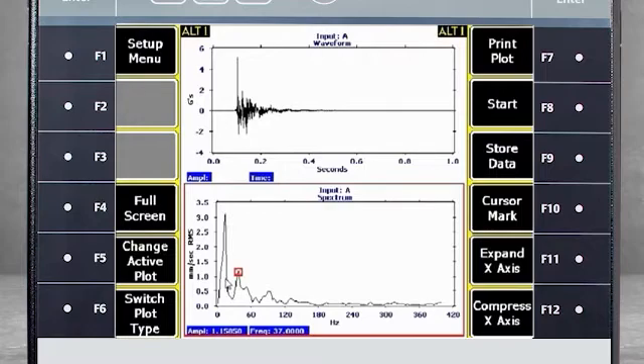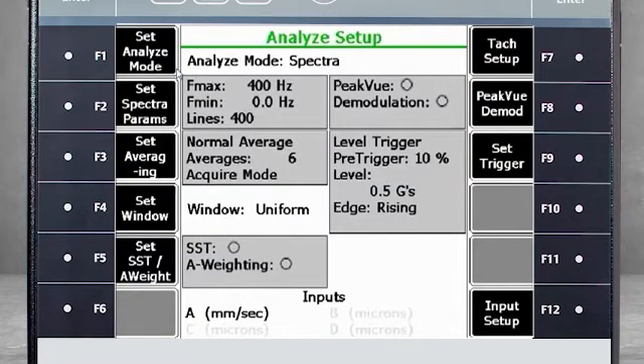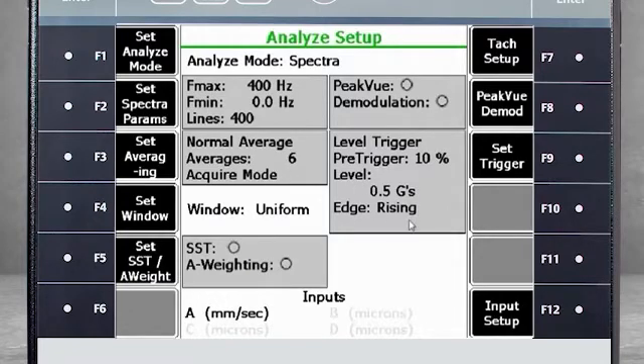This tutorial was based on a template in the AMS 2140 and will work for many applications. However, there are two exceptions that may require you to customize the settings. Select F1 Setup Menu. Here you see that the pre-trigger setting is 10%, which you can change using F9. The important thing to notice is the trigger level at 0.5 Gs — this means that after you start collecting data, the analyzer will be waiting to feel a vibration level higher than 0.5 Gs and will then consider that an impact.